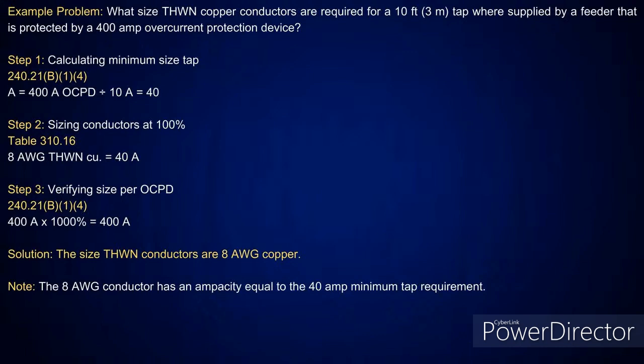So I'm going to size the THW copper conductors, and I've got a 10-foot tap that is protected upstream by a 400 amp overcurrent device. I said 10 foot or less, I divide by what? 10. That gives me 40 amps. I go to table 310.16. The next size in the 75-degree C column above that is a number 8. Then I verify the size of that overcurrent device. When you look at 240.21(B)(1), it says it's 1,000% of the size there. So I have 40 amps times 1,000%, which gives you 400 amps. That's how easy a tap is.